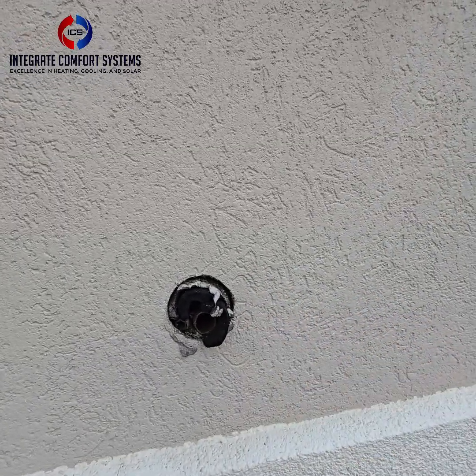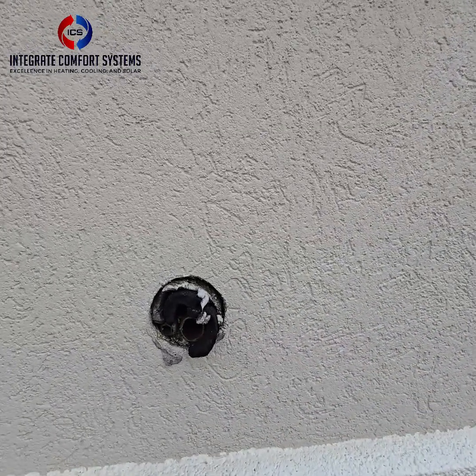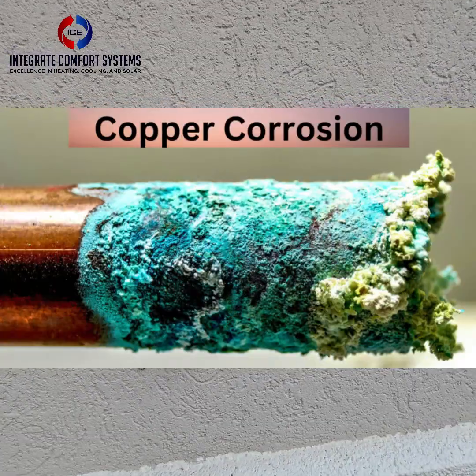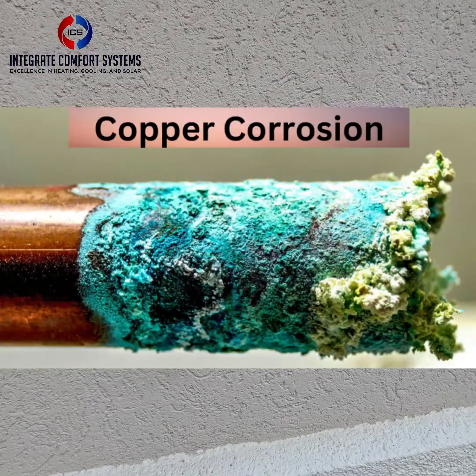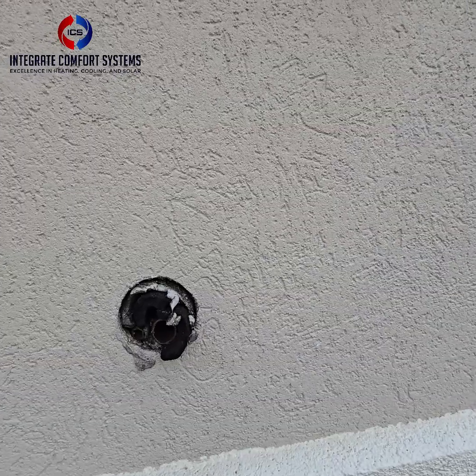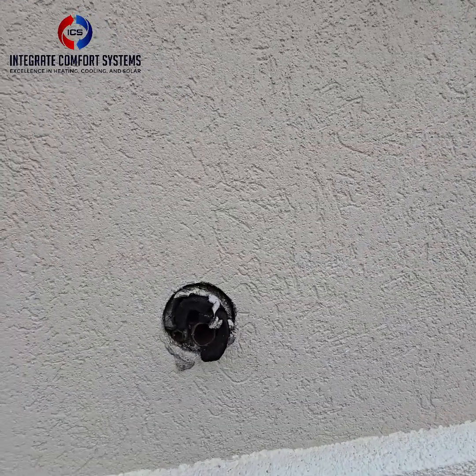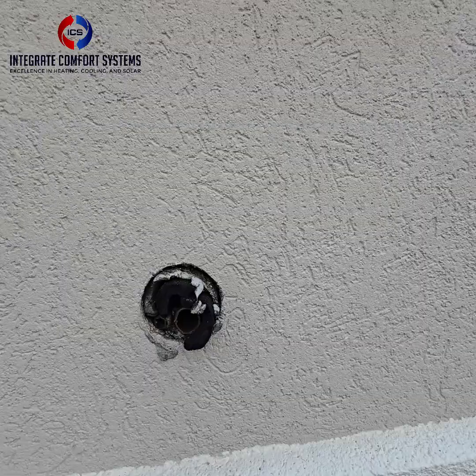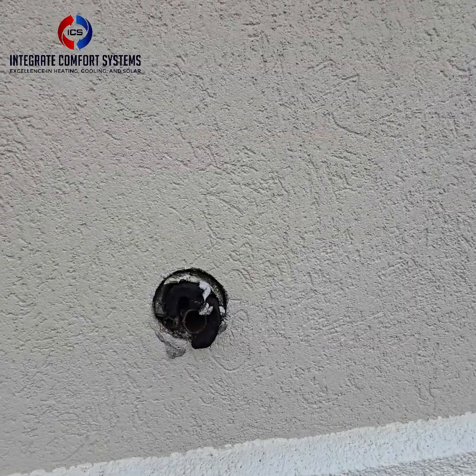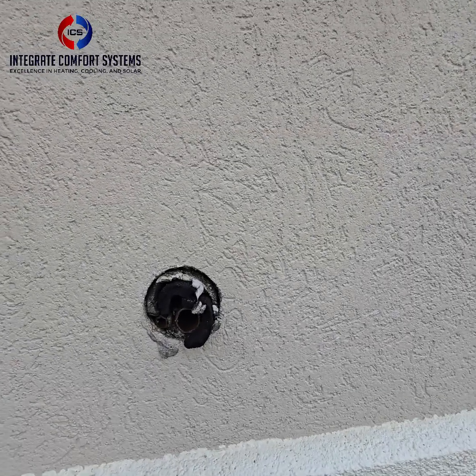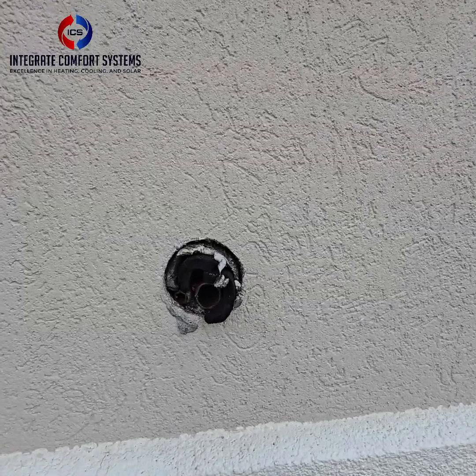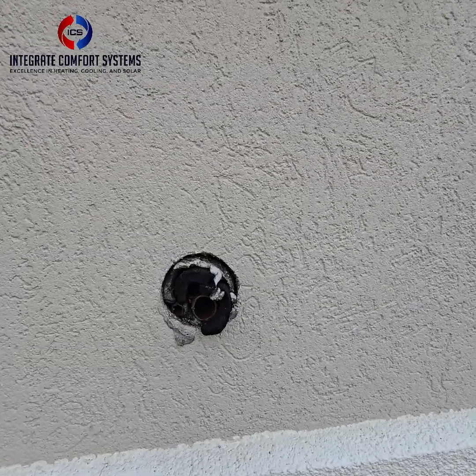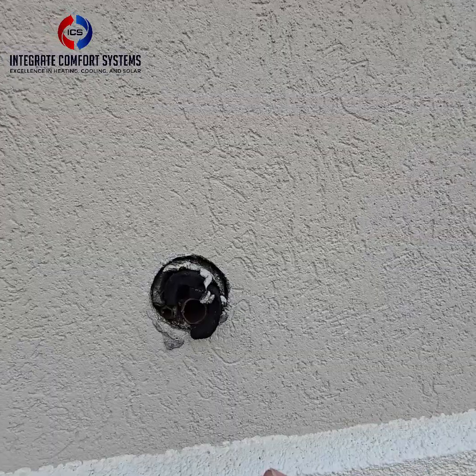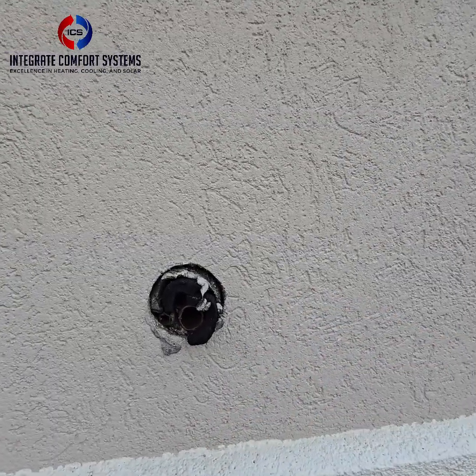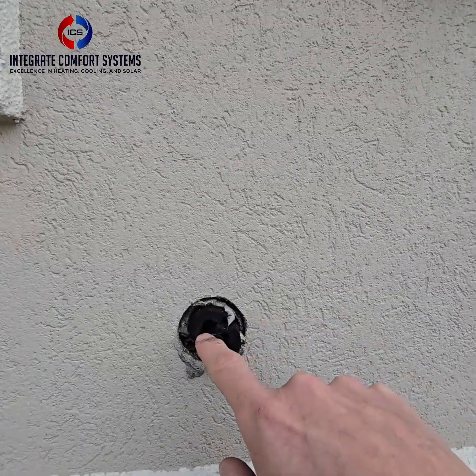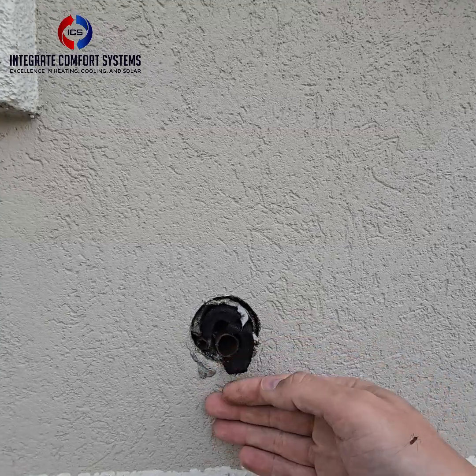What happens is there's a couple things. There's a corrosion risk. Concrete's porous. It can hold moisture, which can accelerate copper corrosion, especially in the presence of salt, acids, and high alkalinity. There's an alkaline reaction, where fresh concrete is highly alkaline, probably something like a pH 12 or 13, which can cause chemical reactions with copper, leading to surface oxidation and corrosion. There's also staining, like when the copper turns green over here, it starts to stain.